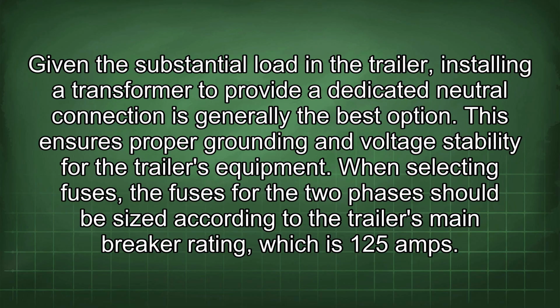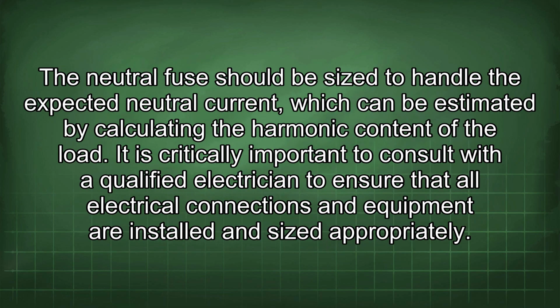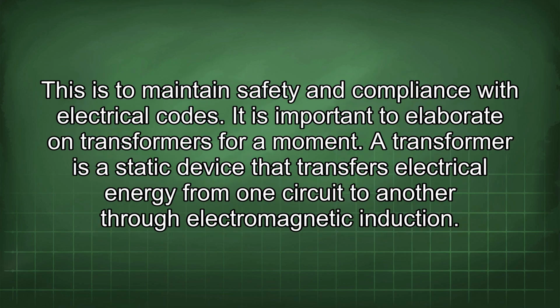When selecting fuses, the fuses for the two phases should be sized according to the trailer's main breaker rating, which is 125 amps. The neutral fuse should be sized to handle the expected neutral current, which can be estimated by calculating the harmonic content of the load. It is critically important to consult with a qualified electrician to ensure that all electrical connections and equipment are installed and sized appropriately. This is to maintain safety and compliance with electrical codes.